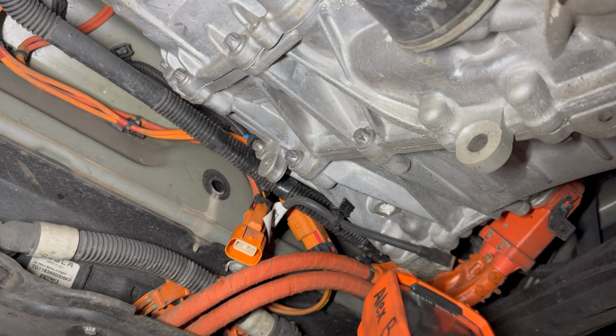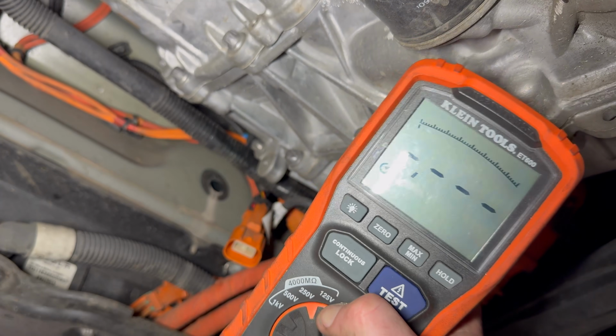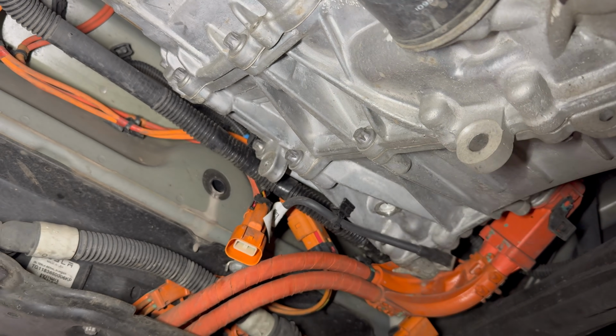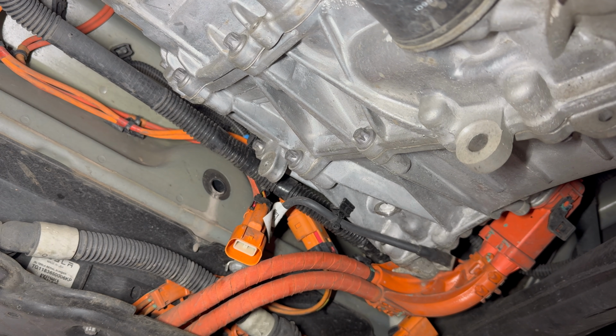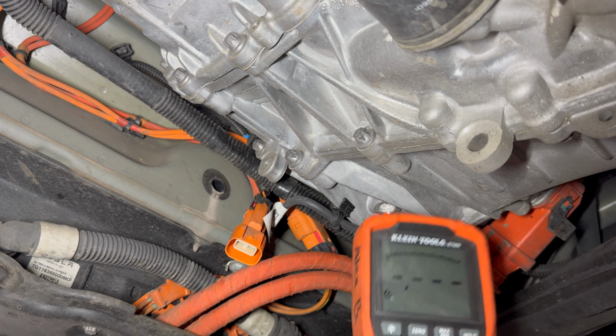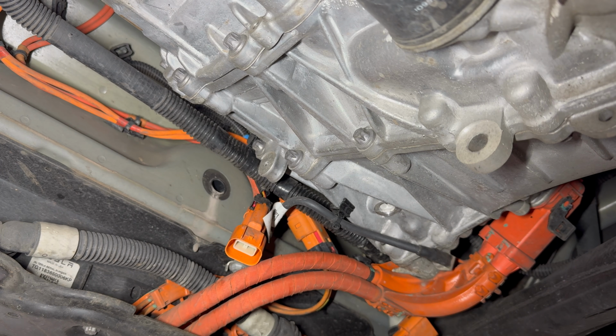Alright, I've got my isolation meter here. On anything like a PTC component on these, you want to run it at 250 volts instead of 500 volts because you don't want to damage any of that stuff if possible. I think I should be able to just ground my negative side clamp anywhere we've got a good ground.